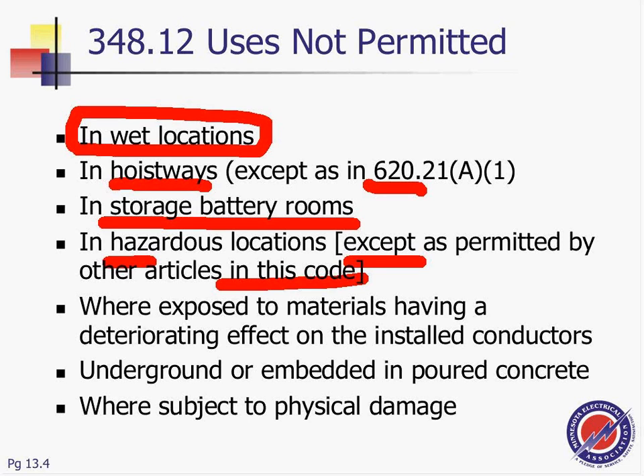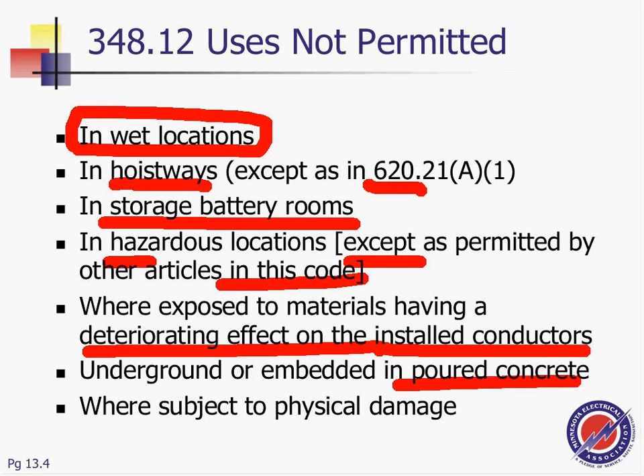Where it's exposed to material having a deteriorating effect on the installed conductors, and I guess that can apply to anything. They don't want you to put it in a place where material can deteriorate the installation, the conductors or the machines. Or embedded in poured concrete. This is not your conduit of choice to bury in concrete, or underground in concrete. Or the most important, physical damage.